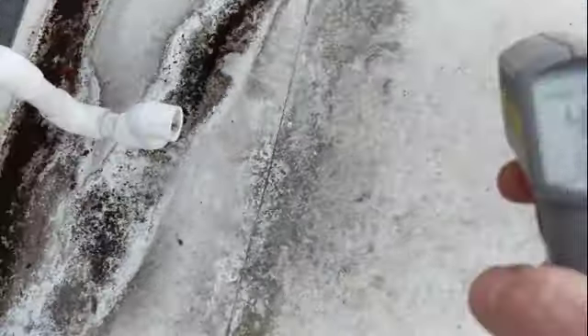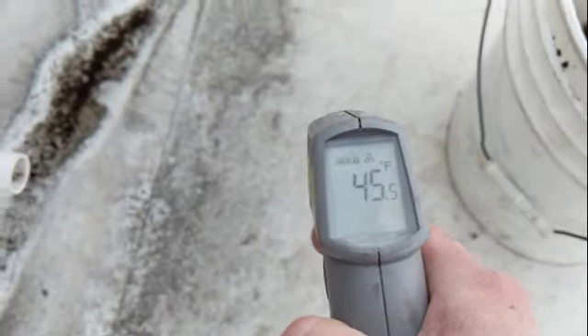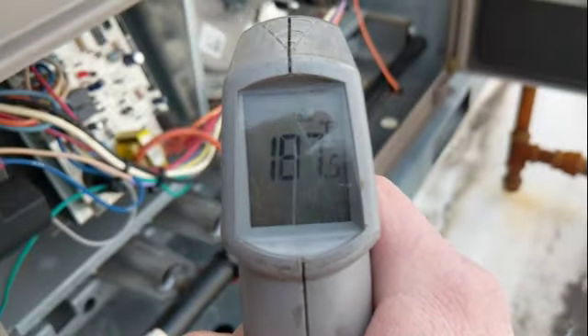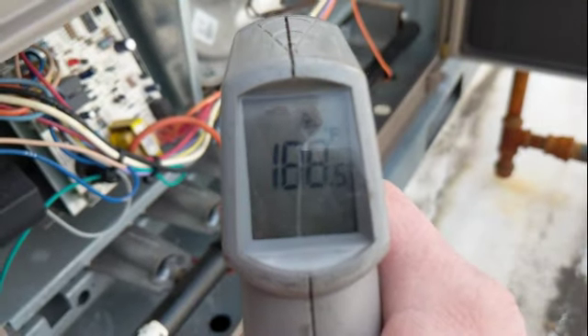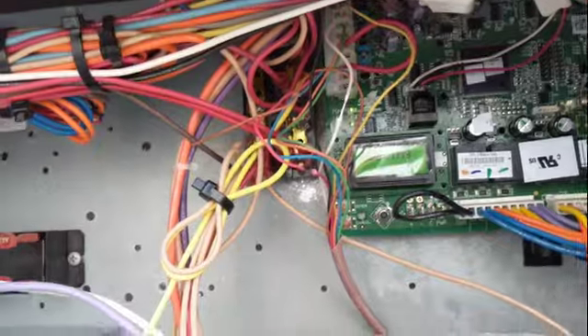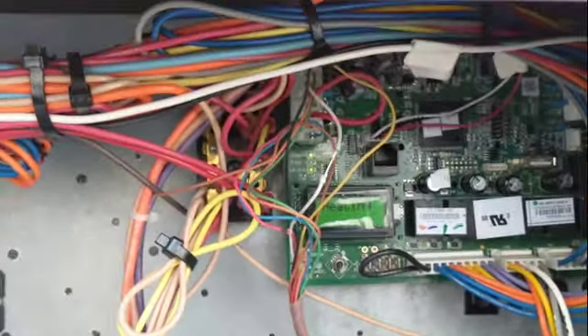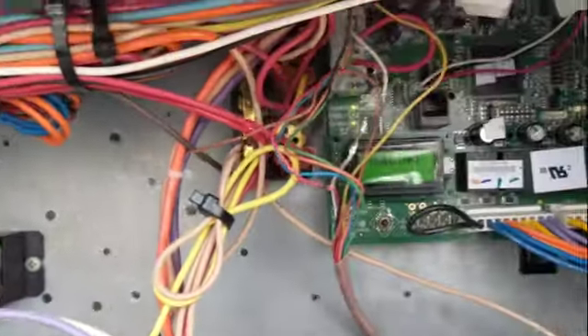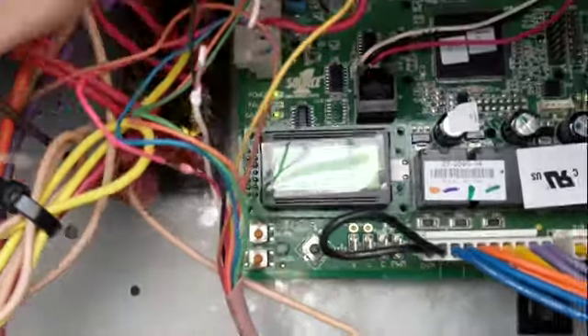It's hot. Just to prove it — it's 45 degrees on the roof and the motor is 190. I'm going to go ahead and cut W, that way this thing's not trying to run heat, burning up that combustion blower anymore.